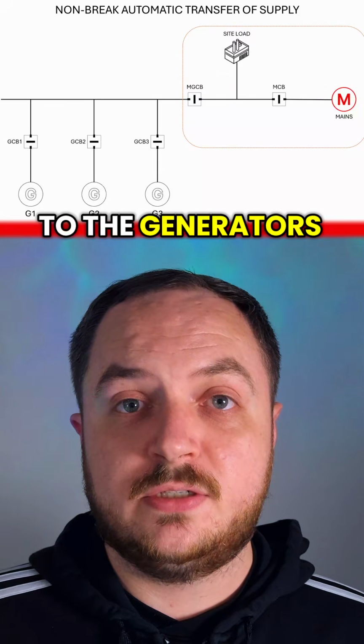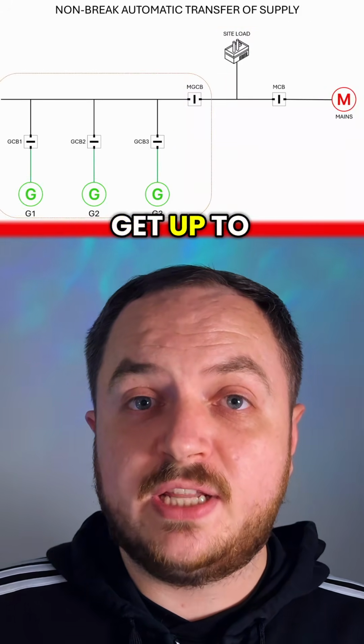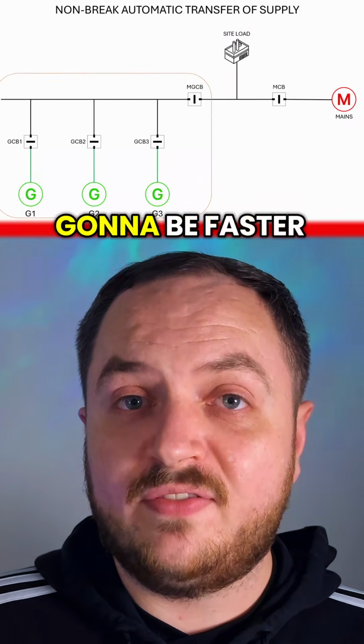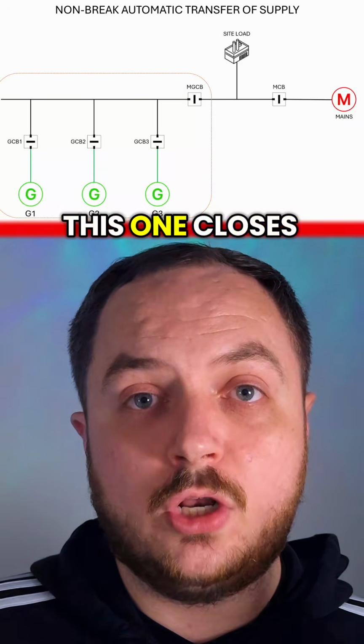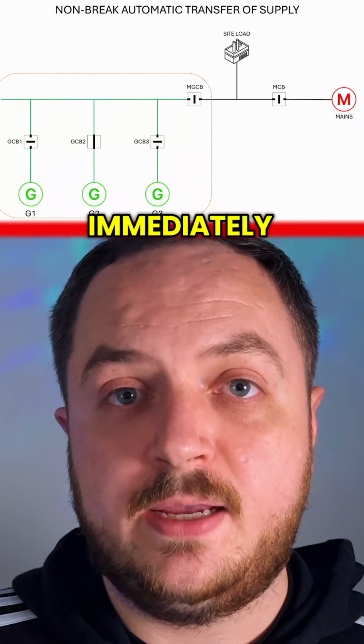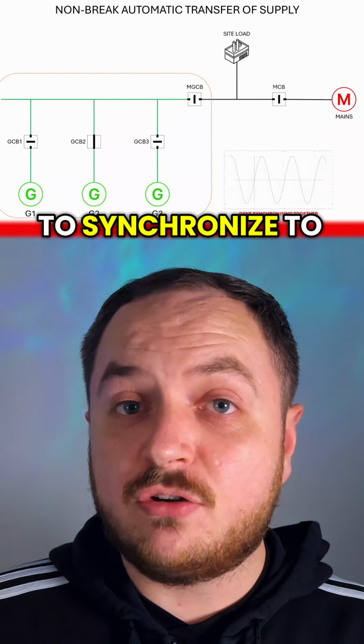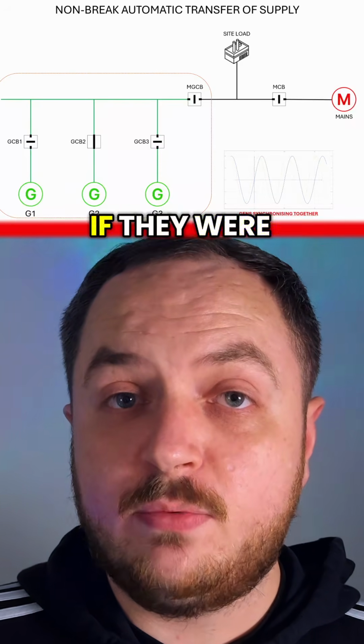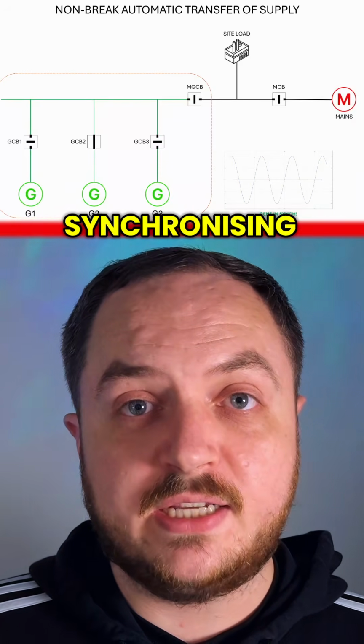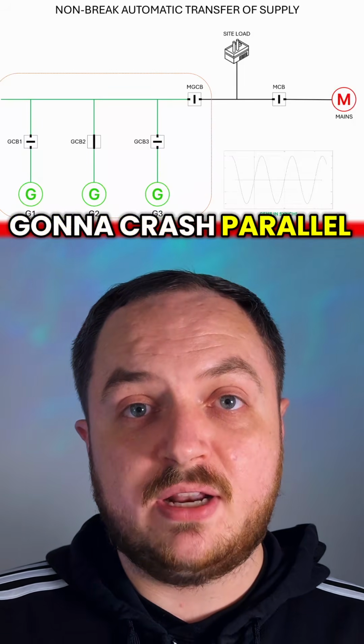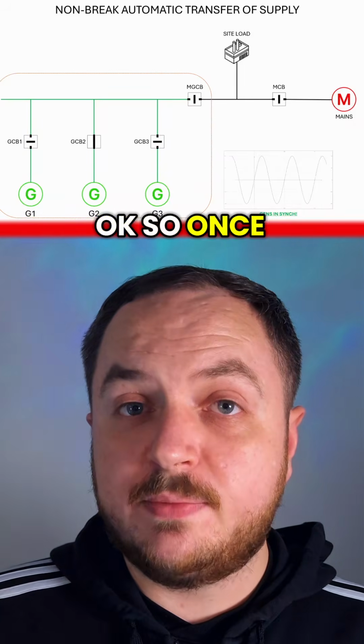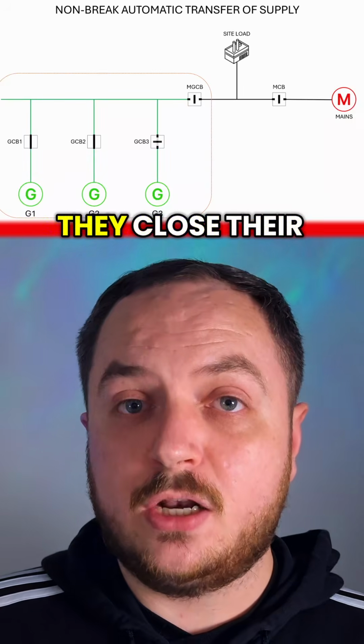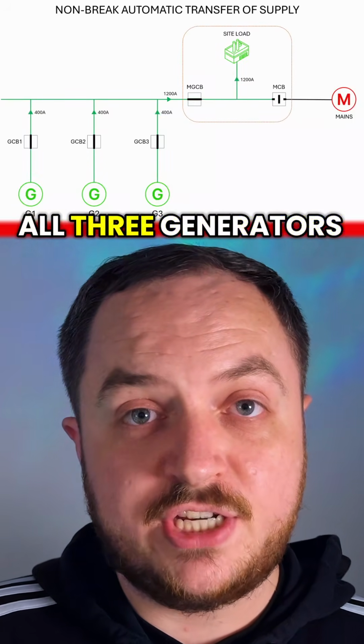to the generators. So those generators then start up, get up to their speed and volts, and one is going to be faster than the others. This one closes its circuit breaker immediately. Those other two generators then have to synchronize to that first generator. If they were to close their breaker without synchronizing, the generators are going to crash parallel and there's going to be damage.